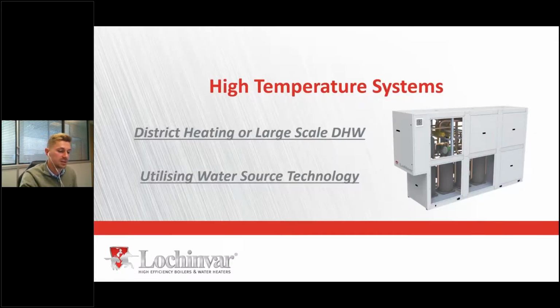Okay, cool. So that's the first section of the seminar. That's electric air source heat pumps. What we're now going to do is look at electric heat pumps, but higher temperature systems. So this is typically going to be high temp new builds, which are fewer and far between now, or even retrofit applications. So if you're looking at maybe the Public Sector Decarbonisation Fund and you're trying to find ways to retrofit into buildings without messing about too much with the emitters, things like that, this is where this is going to fit in really nicely.